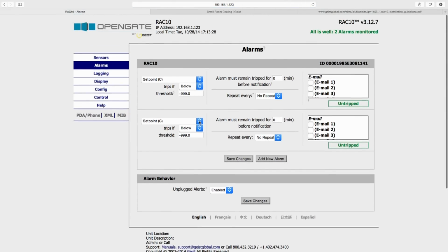We can go down here and take a look at the alarms. This is very useful if you're an administrator dealing with a lot of offices—you can have alarms that send emails or SNMP traps. You can do things like say if the temperature goes above 90 degrees, and have the alarm trip only after, say, 10 minutes, so it doesn't go off willy-nilly, then send an email, and save the changes.